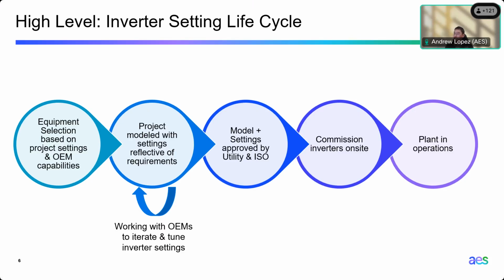Once you can get those tuning settings locked down and it passes most tests, right? Most of the model quality tests and everything like that, right? Then it gets approved by the utility and the ISO, right? Ideally, nothing should change, and you should be able to take those settings and commission those inverters on site with what you studied, right?